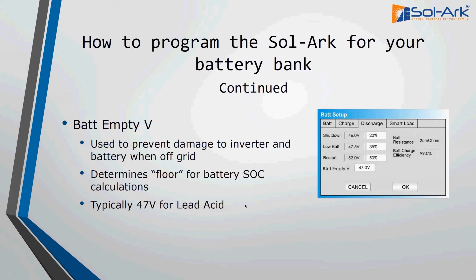And that's a pretty good value for lead-acid batteries. You're going to want to change that depending on what kind of battery you have. And again, we have some examples of what the value needs to be in the manual for a few different brands of batteries. Usually lithium is more like 50 or 51 volts for this value, so just make sure that you're setting that appropriately.